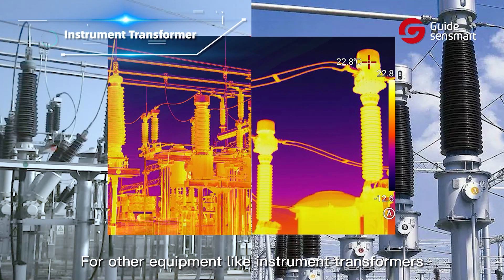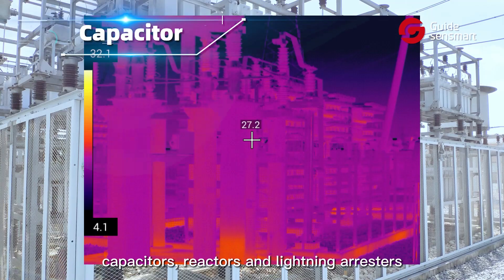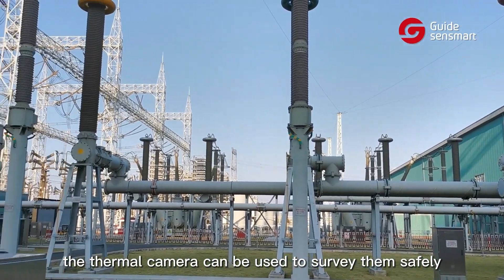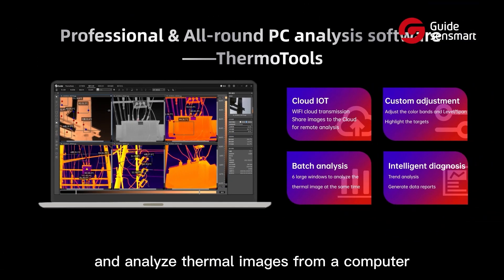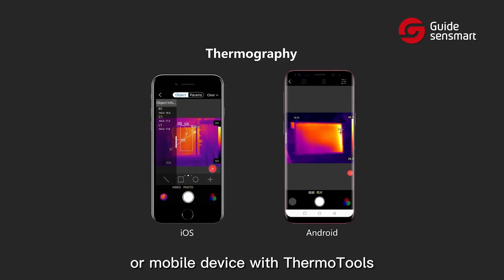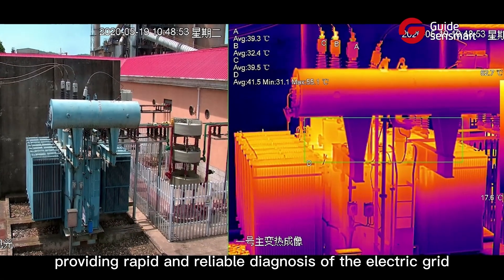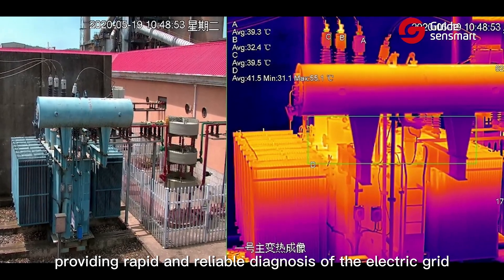For other equipment like instrument transformers, capacitors, reactors, and lightning arresters, the thermal camera can be used to survey them safely and fast, and analyze thermal images from a computer or mobile device with ThermoTools or thermographic software, providing rapid and reliable diagnosis of the electric grid.